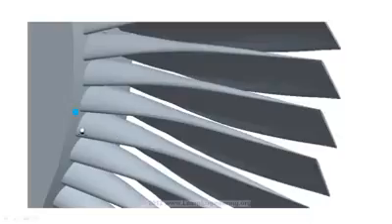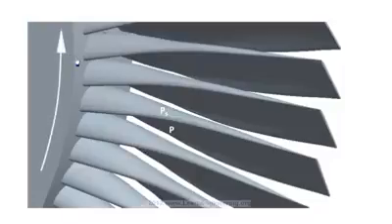When high-energy steam at inlet, the steam with high pressure and temperature, flows over such a blade, it will induce a pressure above and below the blade. And thanks to the special shape of the blade, the pressure above will always be less than the pressure below. So, there will be a resultant net force acting in upward direction. This force will make the blade rotate, in this manner. As the blade rotates, it obviously absorbs some energy from the fluid, so fluid at exit will have less energy compared to inlet. In the coming session we will see how we can predict the energy transfer in the fluid.